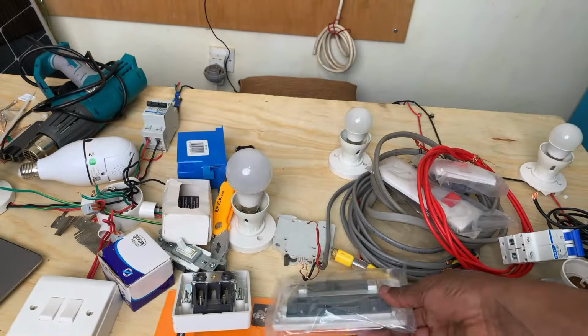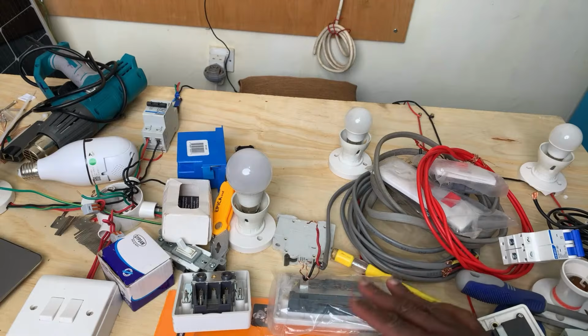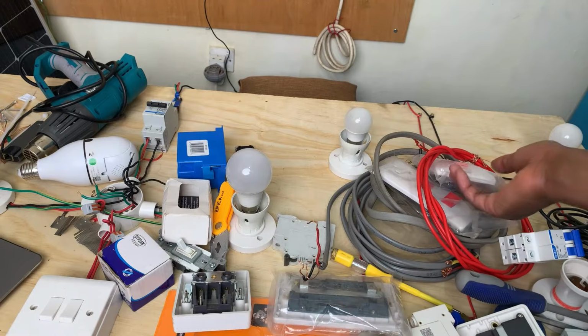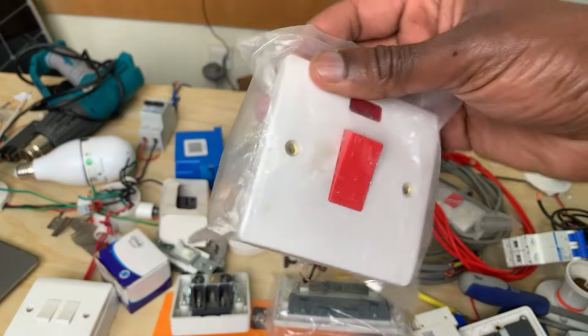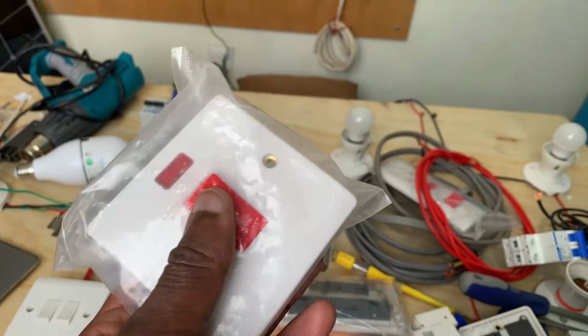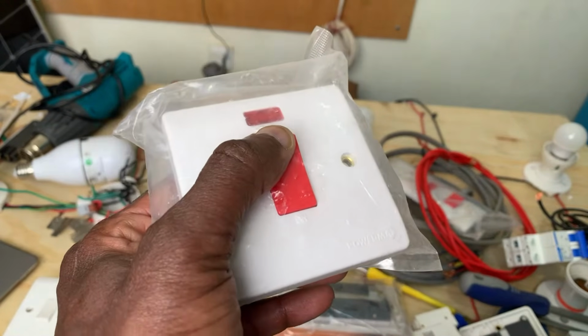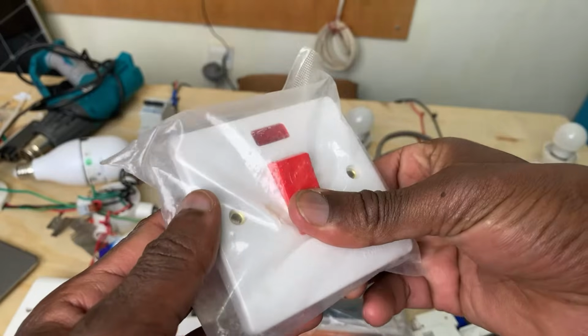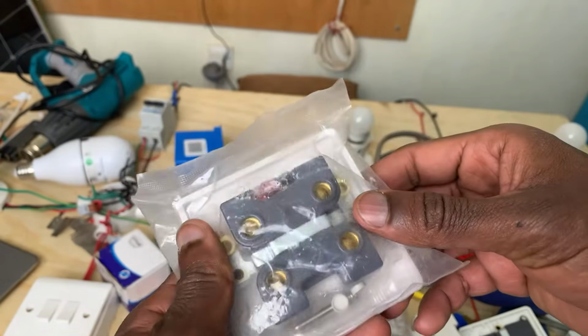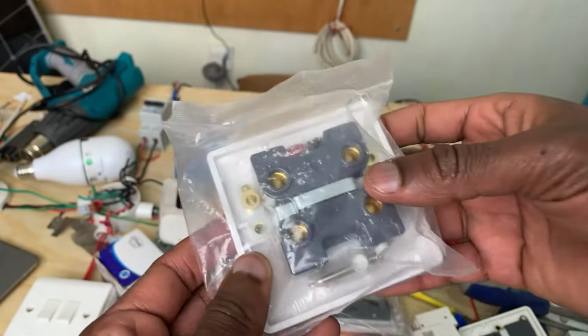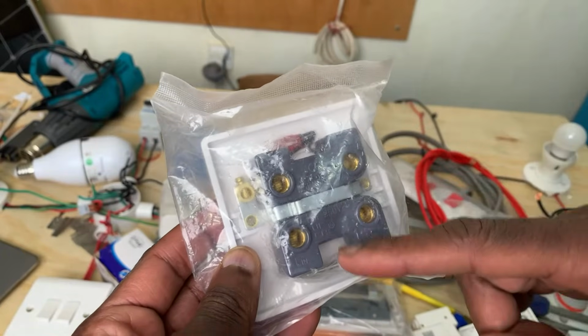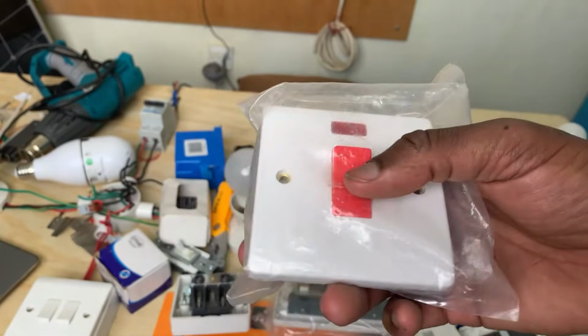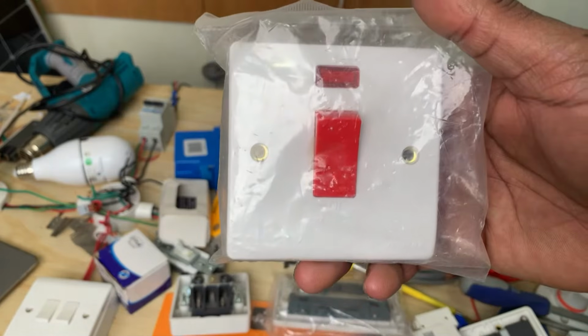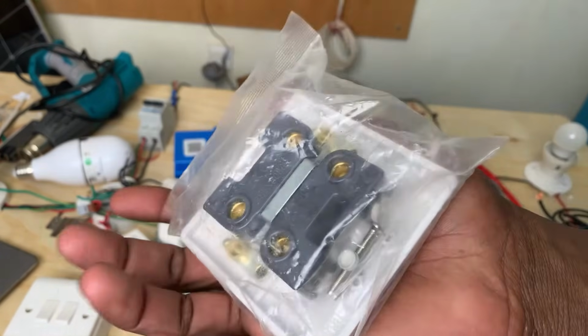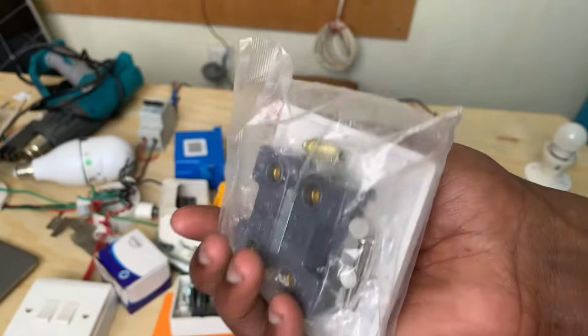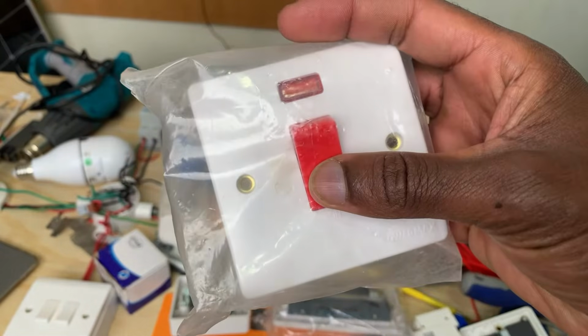So this is the socket, and another thing to watch for is tight or loose connections on the switches, such as this double pole switch. Why is it a double pole? It switches both the line and the neutral. You have to ensure the connection is very tight because these carry heavy loads. This is a 45 ampere switch.